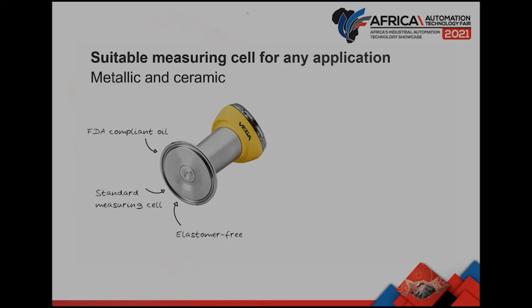So to view the comparison between these two models here, we have the ceramic option on the diaphragm seal on the right-hand side. It's oil-free, very robust and resistant to abrasion. And the metallic diaphragm is also suitable for applications where the ceramic might not be suitable, and where O-rings or polymer O-rings are not suitable for those applications.